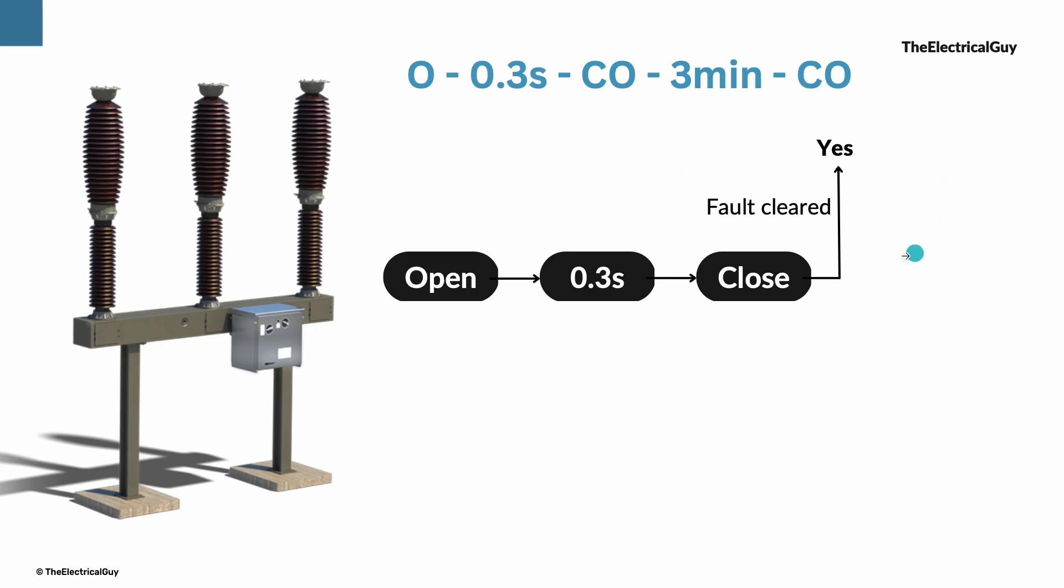But if the fault is still not clear, then breaker will immediately receive an open command.